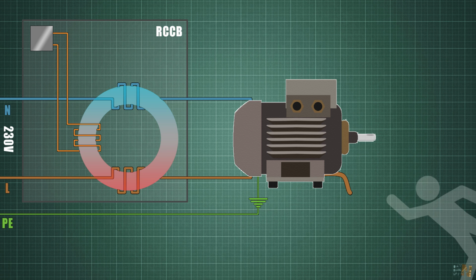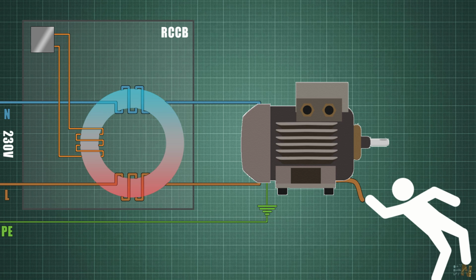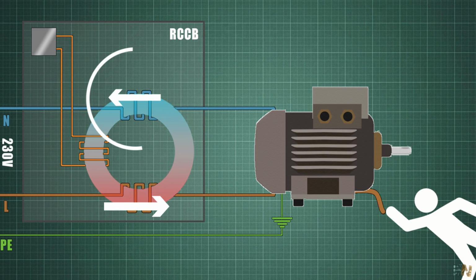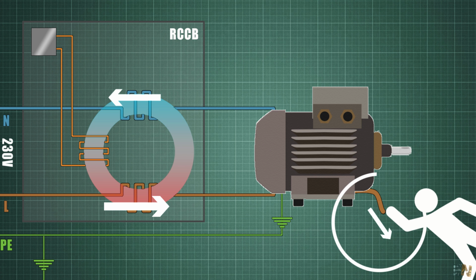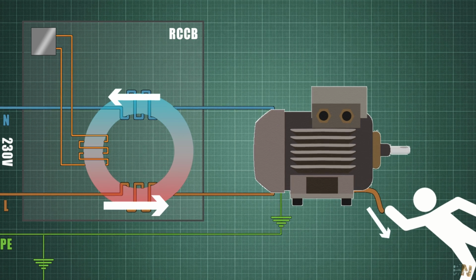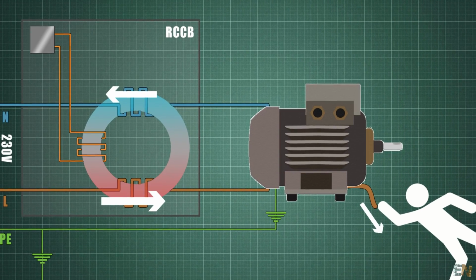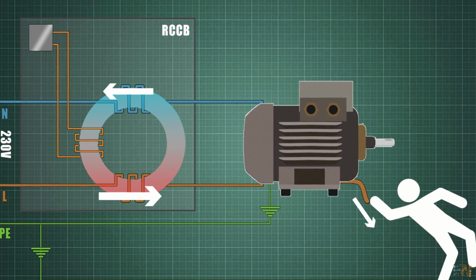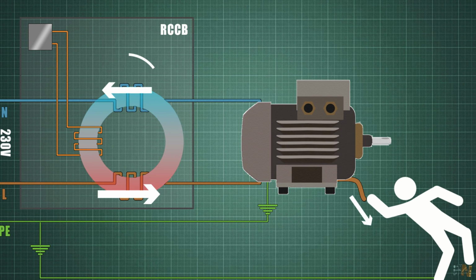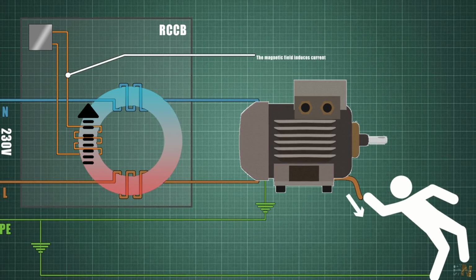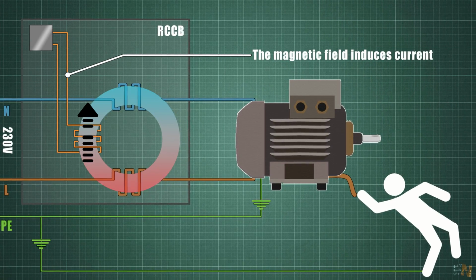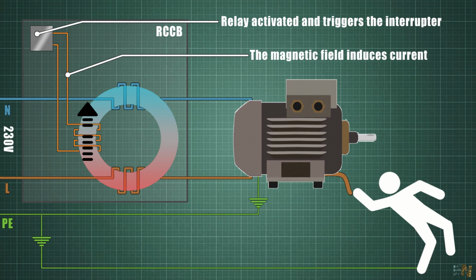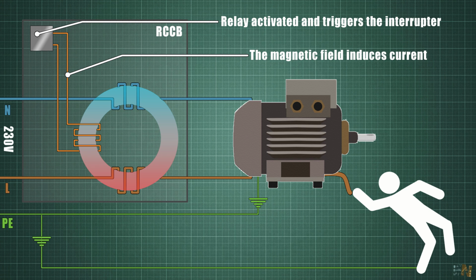But now let's say that I touch the exposed wire. In this exact moment, one part of the current will still be going to neutral as before. But now a small part of the current is also going through me to ground. So as you can see, the input current to the RCCB transformer is not equal to the output current anymore. So the magnetic inductions inside of the core won't cancel each other out. We can easily detect these magnetic induction changes, and when that occurs, we trigger the circuit breaker and interrupt the current flow from the live wires and neutral.